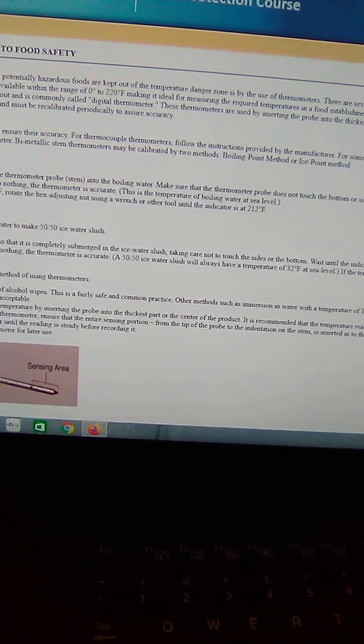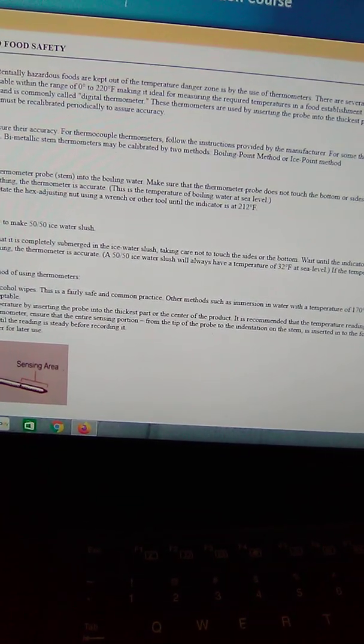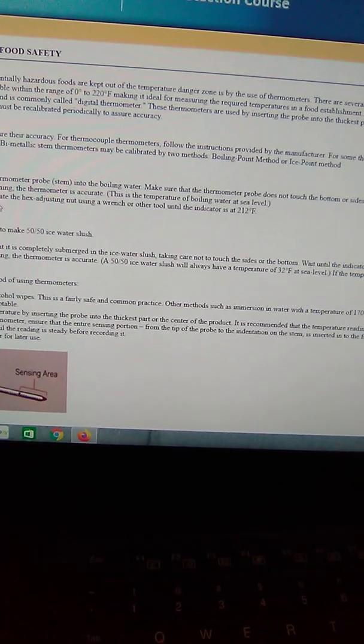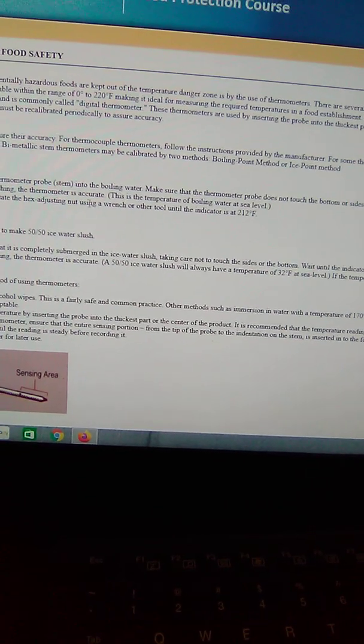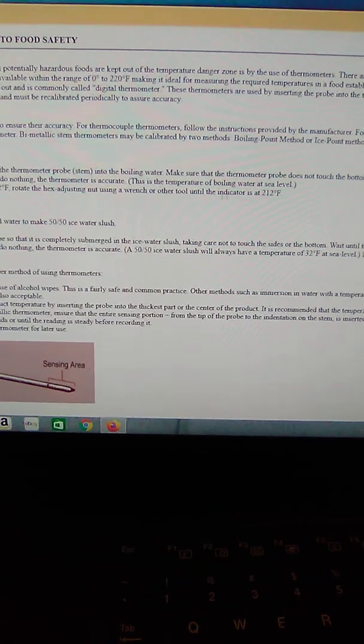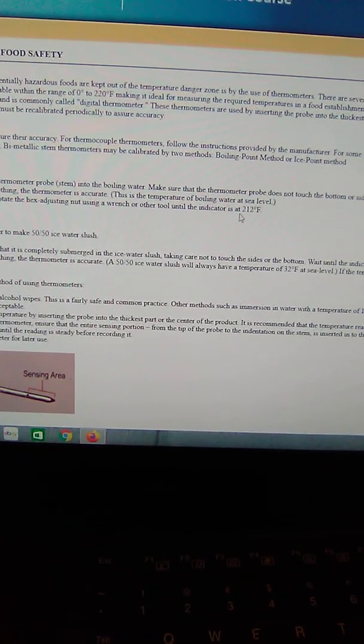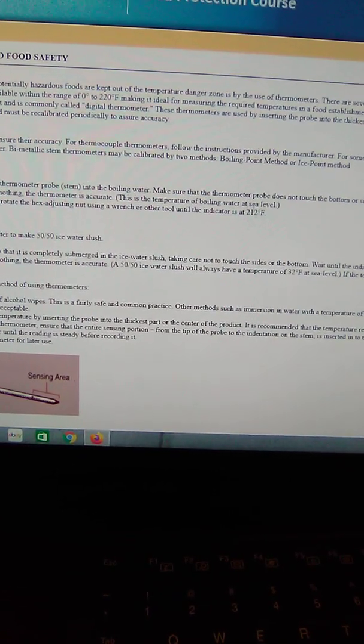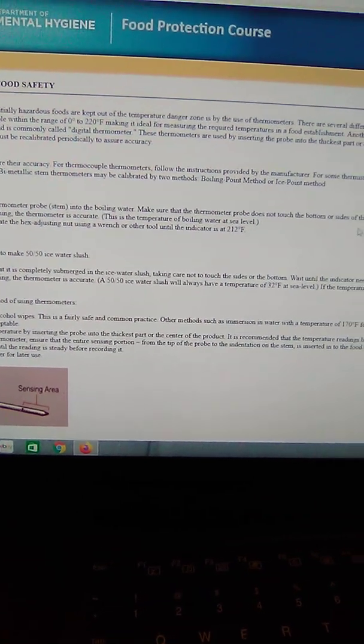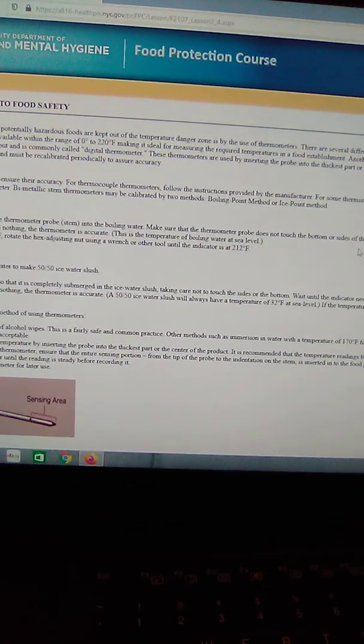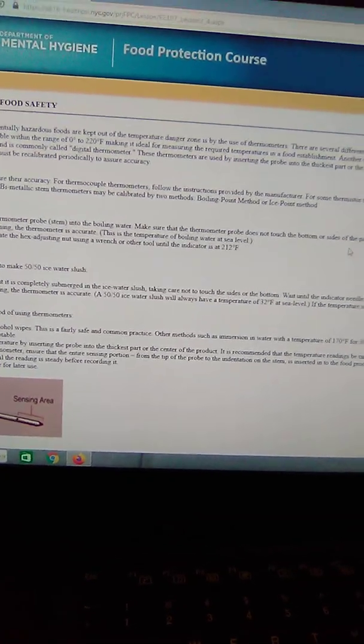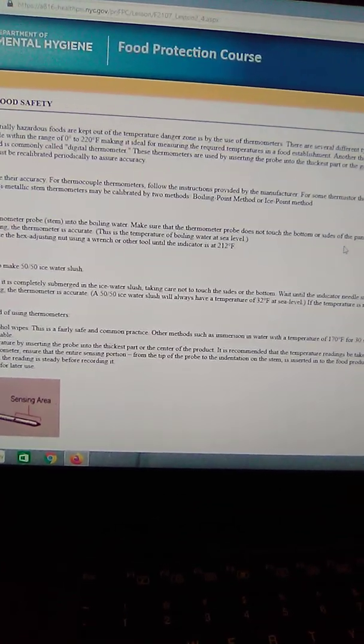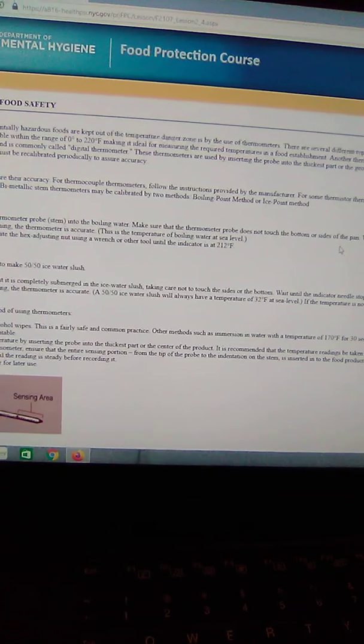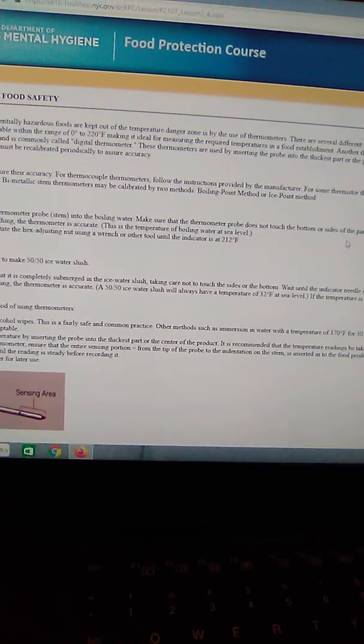If the thermometer is not, and I repeat, is not 212 degrees Fahrenheit, then rotate the hex adjusting nut using a wrench or other tool until the indicator is at 212 degrees Fahrenheit. So when you're using the boiling point method, make sure that the thermometer reads 212 degrees Fahrenheit when the water is boiling. If it's not reading 212, you adjust it so that it reads 212.